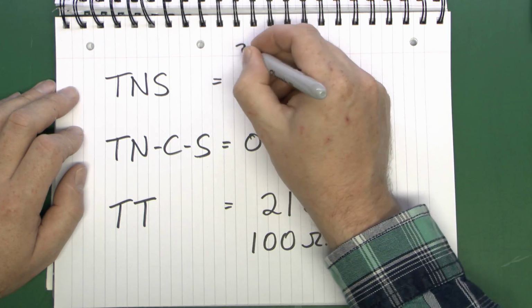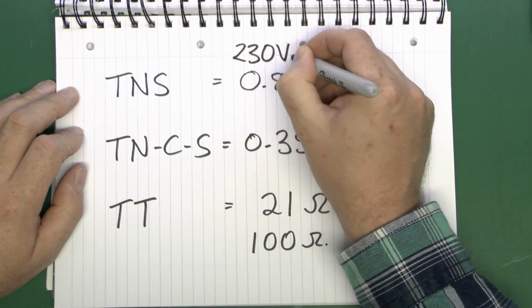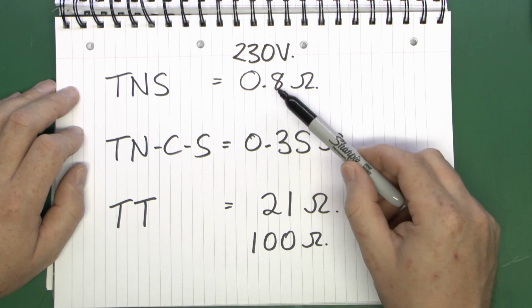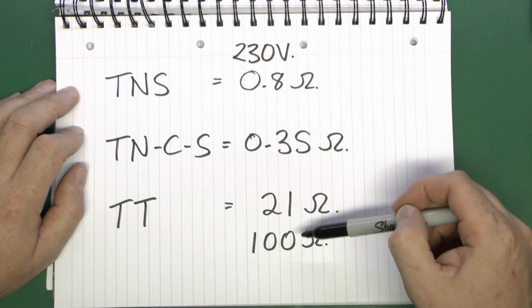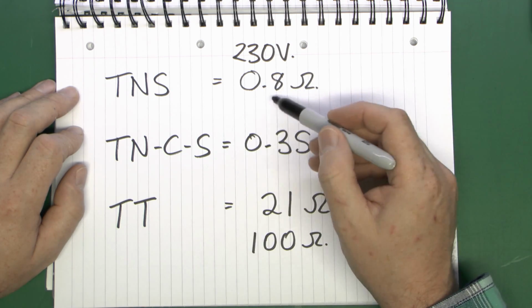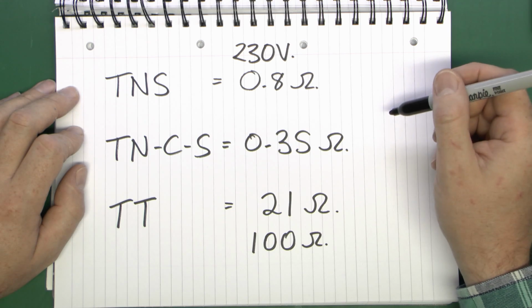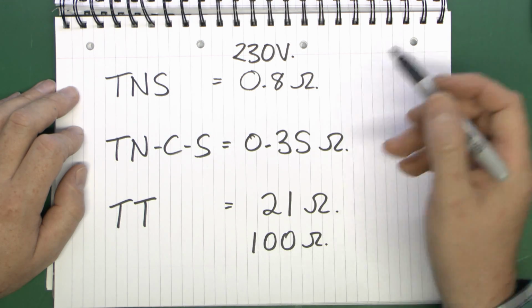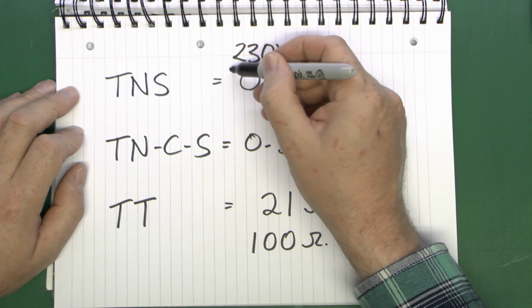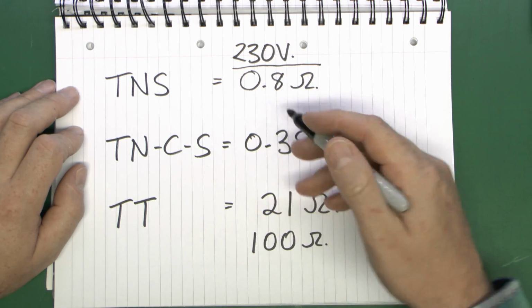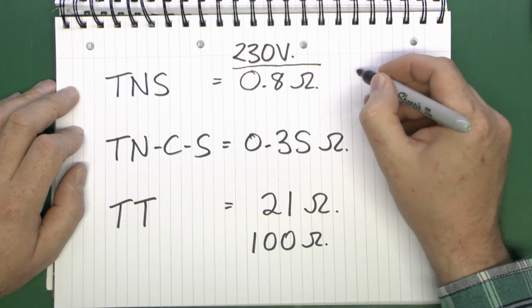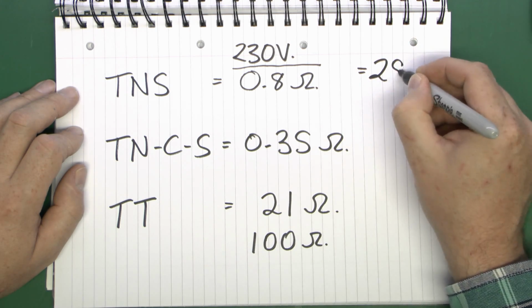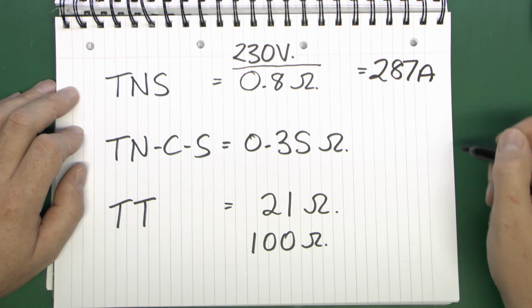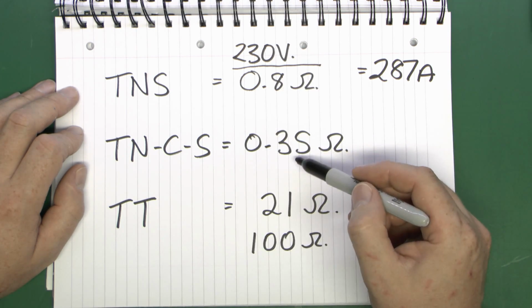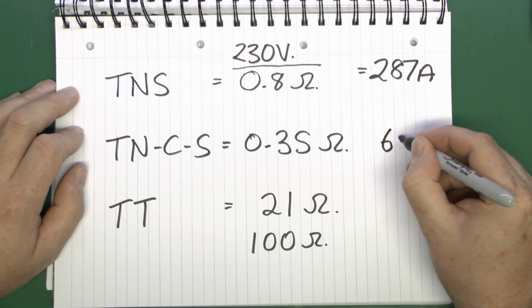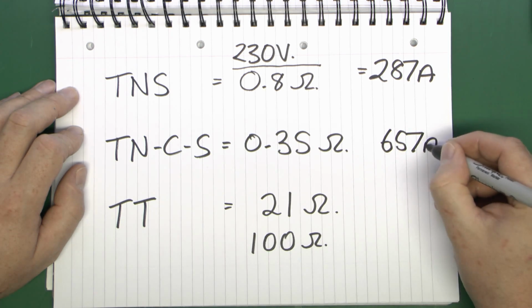Now, for any given voltage, and in the UK that's going to be in the region of 230 volts, if we actually had supplies with these external loop impedances, we can calculate what the current would be in the event of a short circuit fault between line and earth. It's simply the voltage divided by the impedance. So in this case, 230 divided by 0.8 would result in a current of around 287 amps. For this one, 230 divided by 0.35 would be around 657 amps.